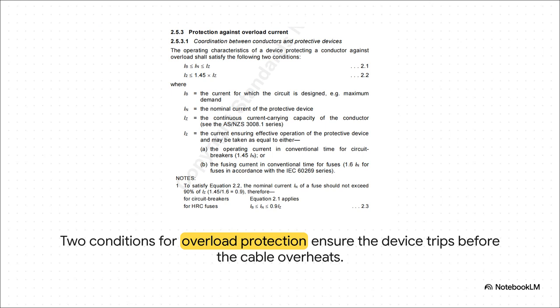Now, this slide looks a bit technical, but it boils down the whole principle of overload protection into two really elegant rules. Let's break them down. The first one basically sets the pecking order. It says your device's rating has to be bigger than the normal load, but smaller than what the cable can handle. Simple enough, right? But the second condition is the real safety check. It makes sure that the current that's guaranteed to trip your breaker is still low enough that it won't cook the cable's insulation over the long haul. It's all about this perfect dance between the cable and the device that's protecting it.